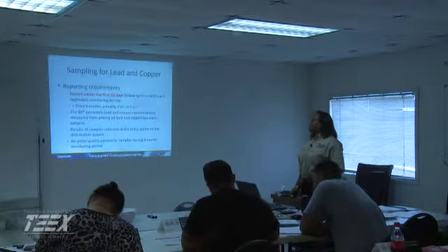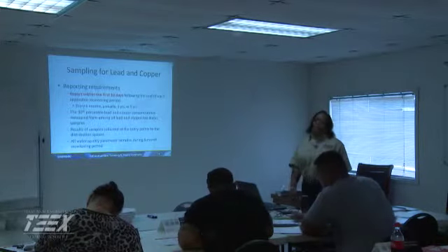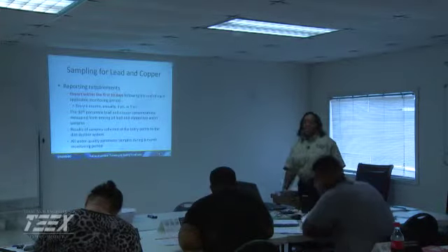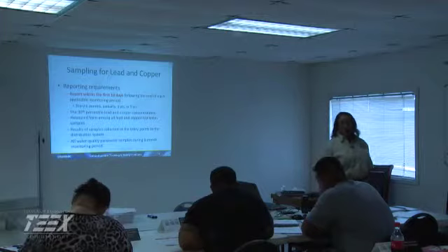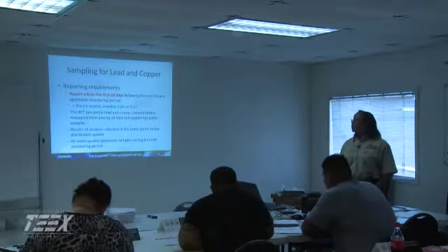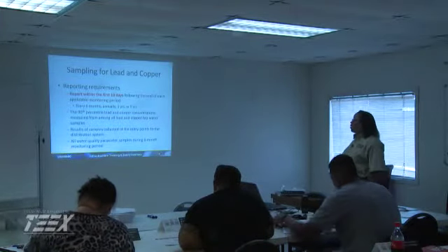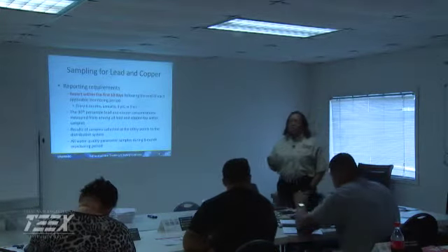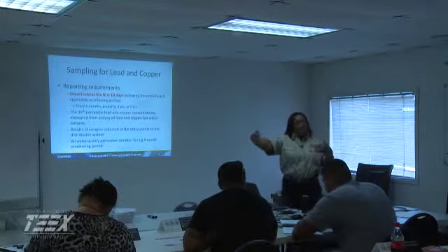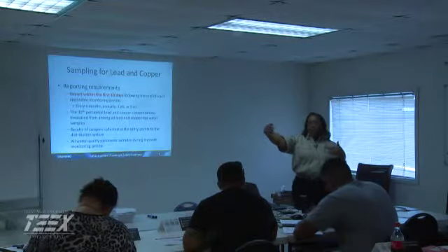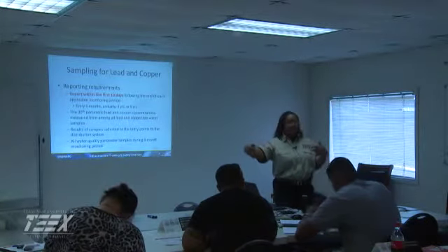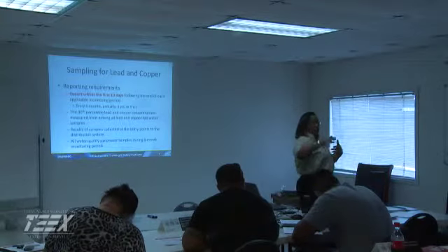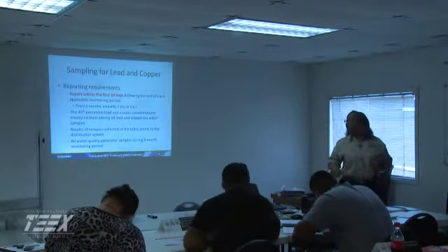So reporting, how do we report the results that we've gotten? We've run the analysis, we've gotten our results, now we're responsible for reporting. You have to report within the first 10 days following the end of each monitoring period. So if you're doing the 6 months, what's today? Today is October the 10th. 10 days from now, I've gotten the results in and have to report my results.